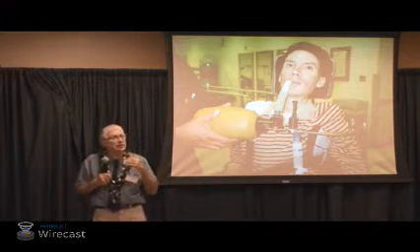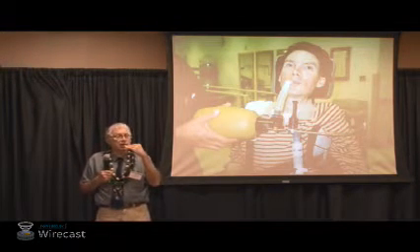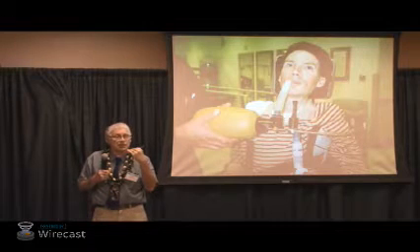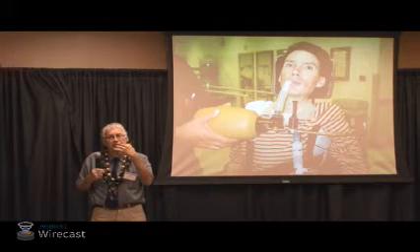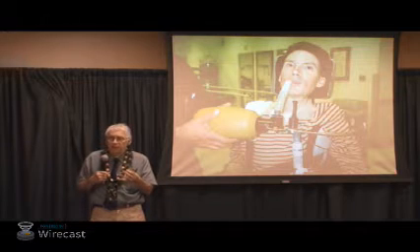If you set a pressure, you cannot air stack. What do I mean by air stacking? Well, you get a volume of air and you don't exhale, you hold it. Now, the machine wants to deliver another volume, but it's set for a pressure of 20 centimeters, let's say. So you're holding 20 centimeters in your lung right now with the first breath. As soon as you open your throat, the machine feels the 20 centimeters and it shuts off. You cannot get another volume of air.